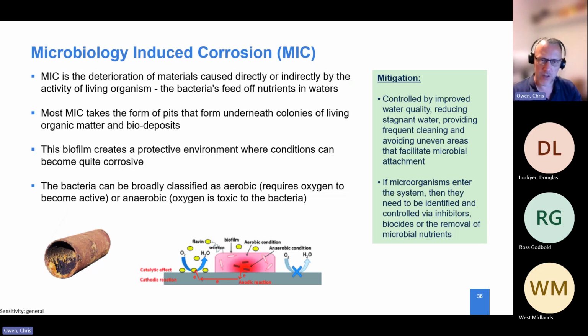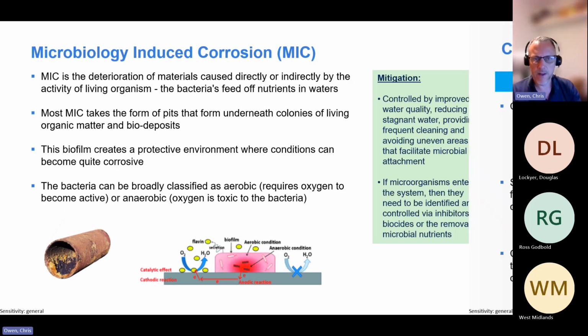Pipework was being commissioned, basically water tested, and then drained down. It was leaving water behind, which was then breaking down to produce these biofilms. Those biofilms were then not becoming stable. They were basically active, and because of the thin wall, they were resulting in very localized pinhole corrosion. So again, understanding what's in your system, and understanding that if you are doing flushing, there are certain things which can be added to try and reduce the risk of biofilms taking place.